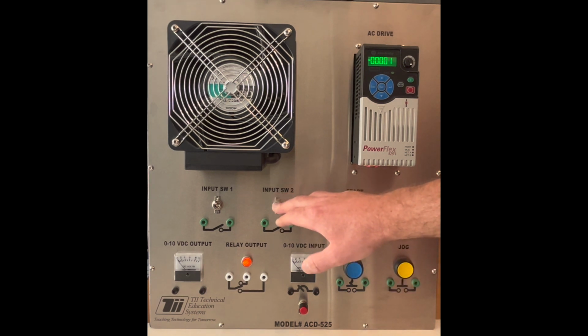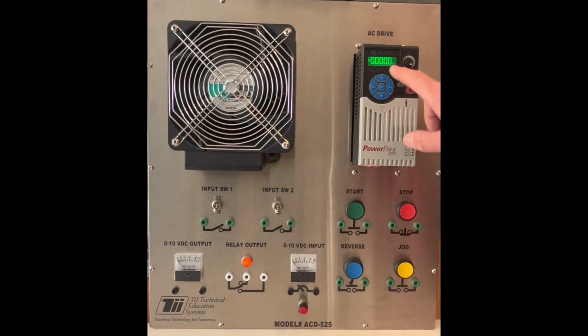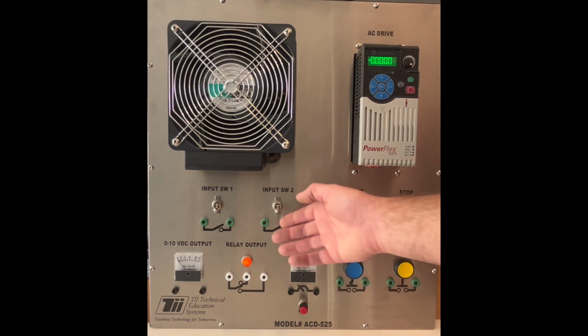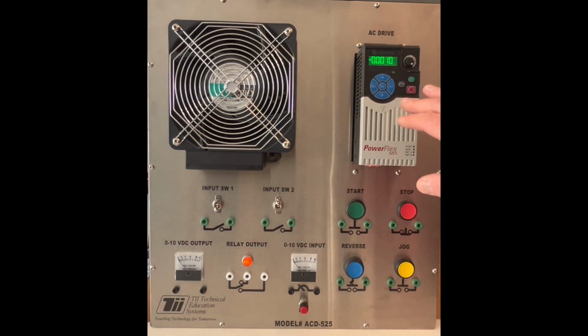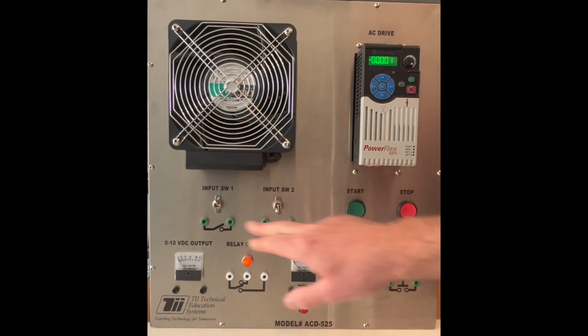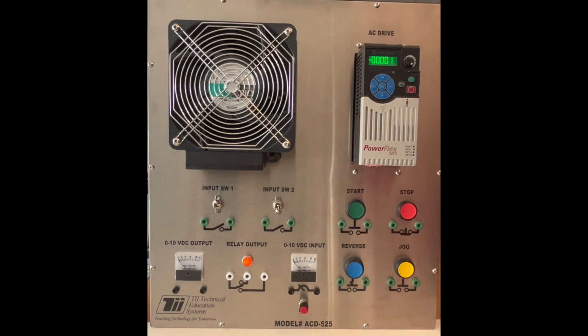Now these are important to know because the reason you may need to come in and check this is that these have the power, if you activate them with the settings that you'll learn in later videos, to override the parameters that are set in the VFD. So for example, if switch 1 is activated here, this may change the maximum frequency that the VFD is allowed to speed up to.